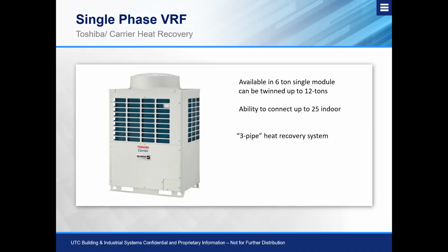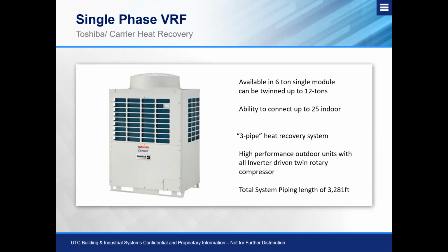So we think back earlier to the slides that we went over. This has that separation process or allows that simultaneous heating or cooling in the outdoor unit, which is why we have 3 pipes on the system: hot gas, liquid, and suction. And again, this has those high performance outdoor units with the inverter driven rotary compressors. And we still offer 2 per outdoor unit, not only for redundancy, but also to increase low ambient heating performance. And just like the 3-phase product line, we still have a total system piping length of 3,281 feet total to work with. So we certainly have flexibility on residential and light commercial applications that we can look at applying this equipment to.